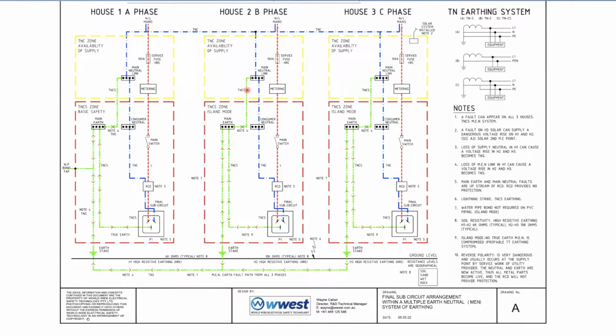And we come down here, we've got the TNCS link, which is called the M.E.N link, down to the main earth. But look, if you look at it, there's no copper piping. And this is a change that's happened to the electrical standards since about the early 1990s, where polybutylene replaced copper piping for the taps, the gas, all your earthing arrangements, and galvanised piping is now PVC. So effectively, you've got your TNCS zone, which is over here, your basic safety zone.